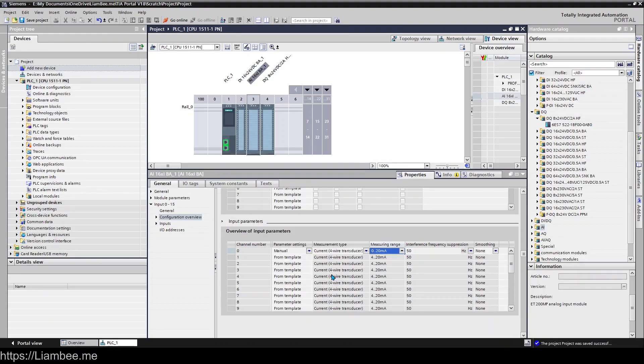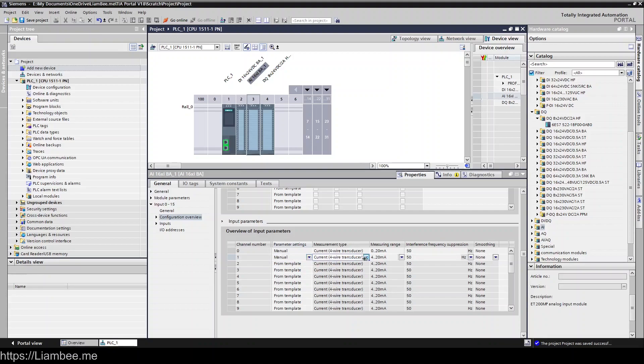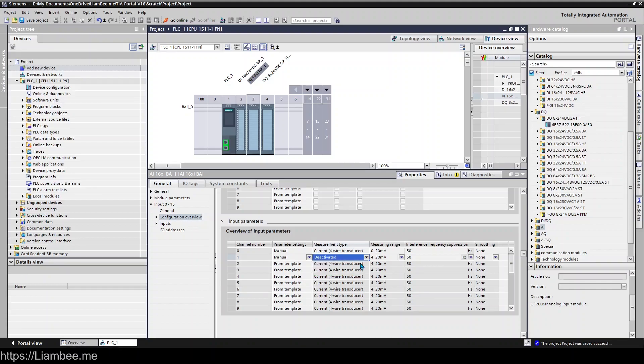One of the things with analog inputs is to remember that if you're not using it and you have things like wire break turned on or the diagnostics turned on, that you should come into here and put it in manual and then set the measurement type to disabled. Otherwise, you're going to find that your card is throwing errors saying that you've got an open loop or a low milliamp reading because you've got nothing connected to it.